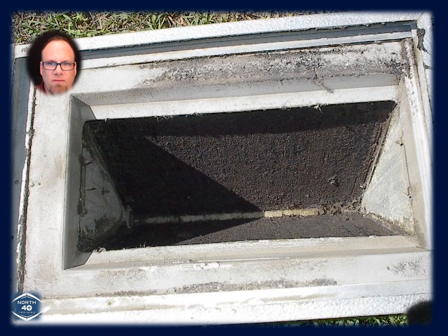Well, it couldn't get rid of the airflow, and that's a big problem. When you can't get rid of the airflow, you can't get rid of the heat. So you've got to think about those things when you're out there. Think about how quickly this problem could have been solved during that installation. Now, sure, it might slow you down for 10, 15 minutes while you clean this thing out, but that's not nearly the amount of time that was spent afterwards in the several trips and also getting the technical department and almost the manufacturer involved with the situation and getting egg on your face, because in reality, the problem was yours, not the equipment at all.